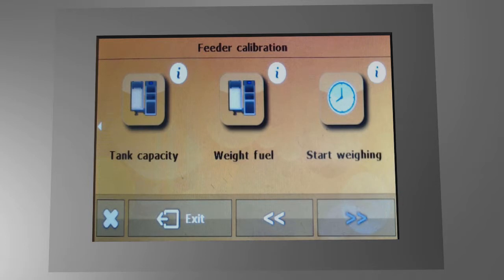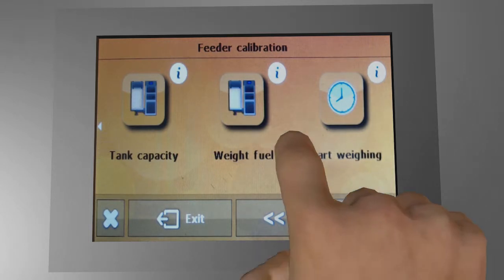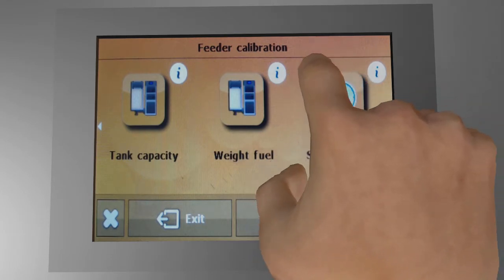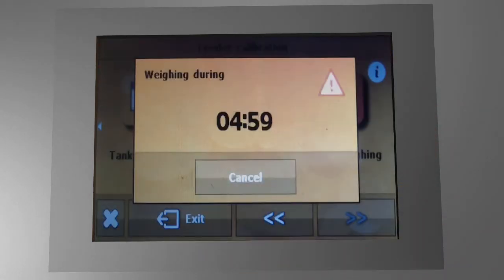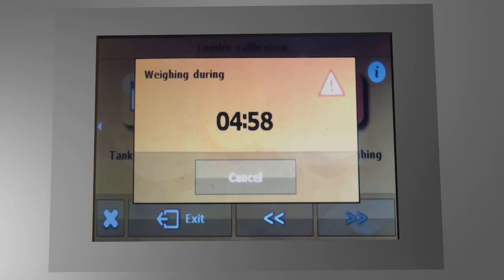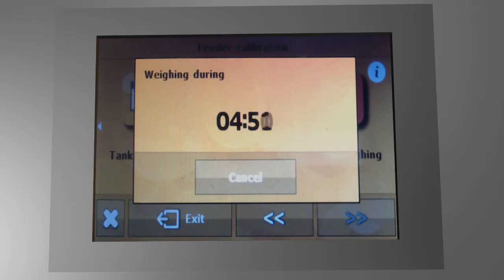Now we need to measure how many pellets your feeder is able to supply in a 5-minute time interval. First, activate the start weighing function. Then get yourself a plastic sack or paper bag and hold it in front of the feeder outlet.